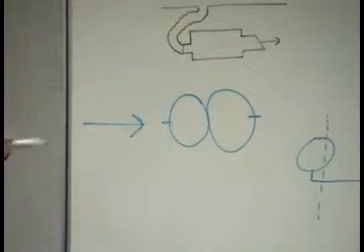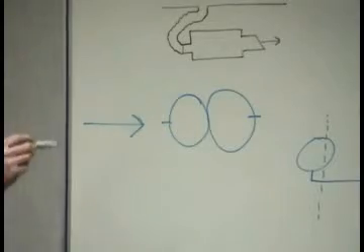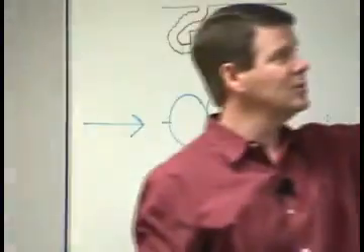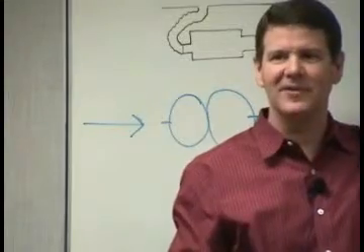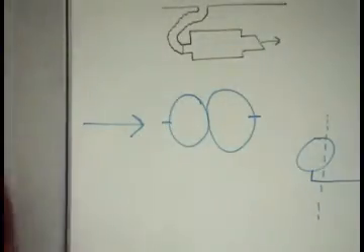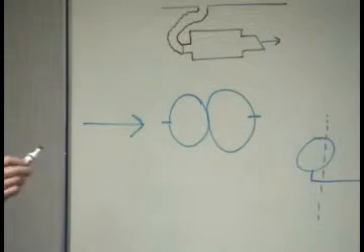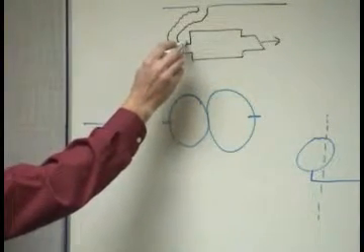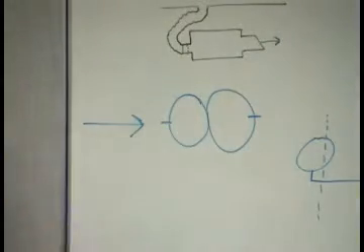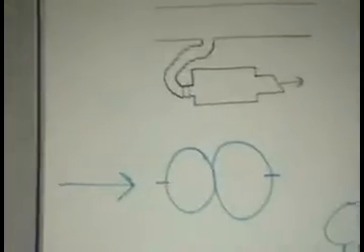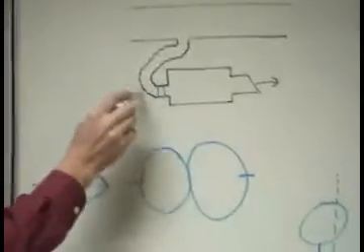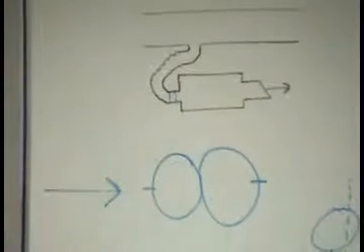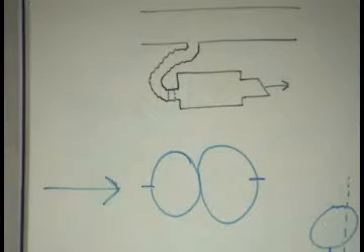We're about out of time here, but a couple things quick I wanted to touch on. If I tell this to Titus or whatever box manufacturer, they're going to come back and say, oh no, not our boxes. We have a special pickup, here's my box here, in the inlet. They always have theirs in the inlet, which is usually about this far away from the damper. And then they go on to tell you in the instructions that we want 3 duct diameters of straight duct in front of that pitot tube.